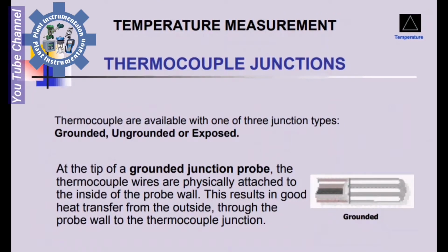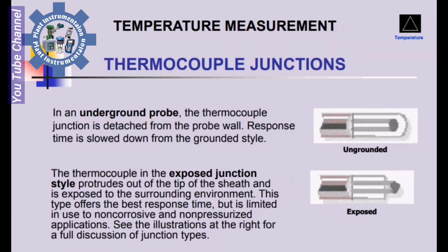Junctions. Thermocouples are available with one of three junction types: grounded, ungrounded, or exposed. At the tip of a grounded junction probe, the thermocouple's wires are physically attached to the inside of the probe wall. This results in good heat transfer from the outside through the probe wall to the thermocouple. Ungrounded: in an ungrounded probe, the thermocouple junction is detached from the probe wall. Response time is slowed down from the grounded style. Exposed.